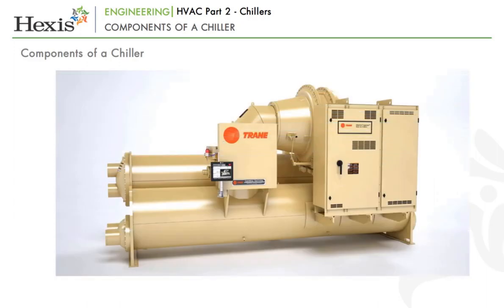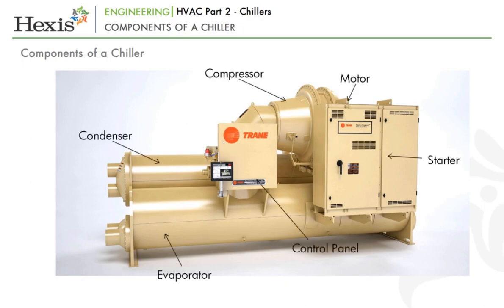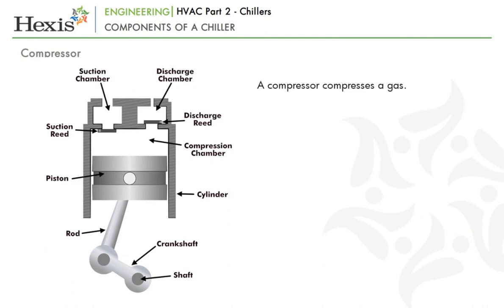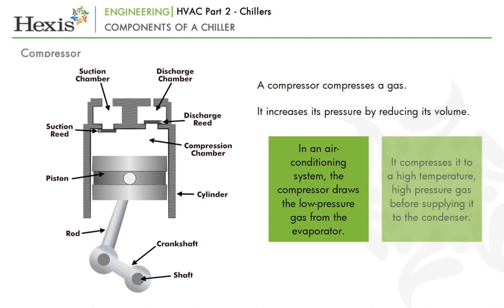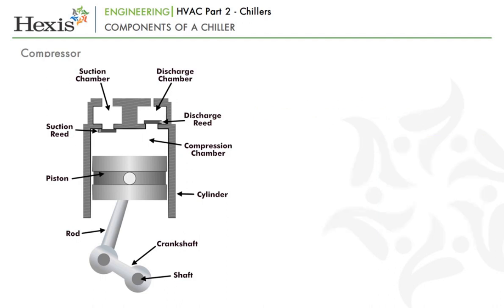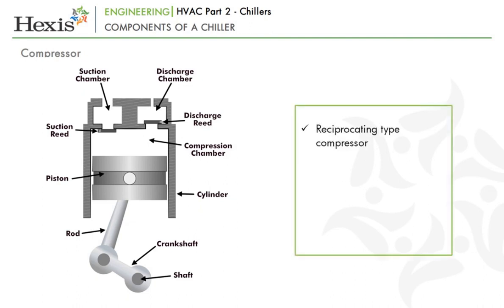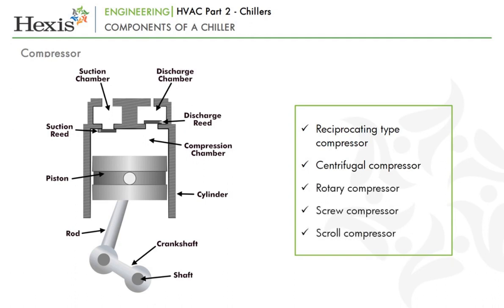Let us now look at the components of a chiller. The main components of a chiller are the same as those of air conditioning systems, namely: compressor, condenser, cooling tower, expansion valve and evaporators. In this topic, we will learn about the types of compressors, condensers and evaporators. A compressor is a device that compresses a gas, increasing its pressure by reducing its volume. In an air conditioning system, the compressor draws the low-pressure gas from the evaporator and compresses it to a high temperature, high-pressure gas before supplying it to the condenser. Different types of compressors used in chillers are: reciprocating type, centrifugal, rotary, screw and scroll compressors.